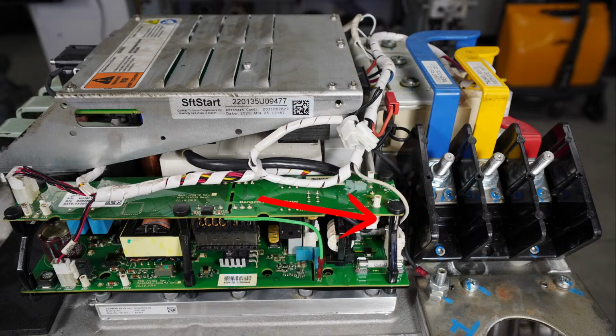Now, if you do have a blown fuse here, or if your breaker or disconnect did trip on the main input power side, then you need to take a lot of care and carefully analyze these SCRs, the capacitors, and potentially -- probably not -- the inverter. If there's an issue, it's probably going to be in the SCRs or maybe a capacitor. But you really want to pay very close attention to the SCRs.